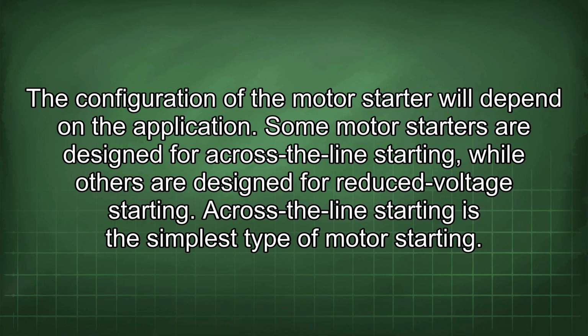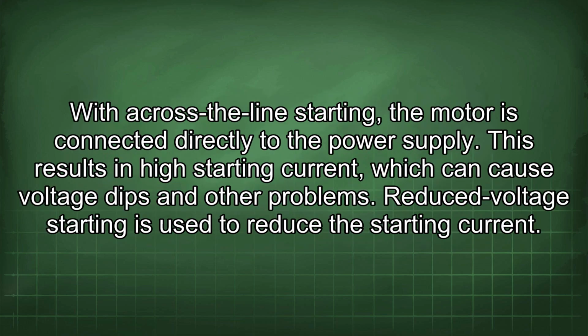Some motor starters are designed for across-the-line starting, while others are designed for reduced voltage starting. Across-the-line starting is the simplest type of motor starting. With across-the-line starting, the motor is connected directly to the power supply. This results in high starting current, which can cause voltage dips and other problems. Reduced voltage starting is used to reduce the starting current.